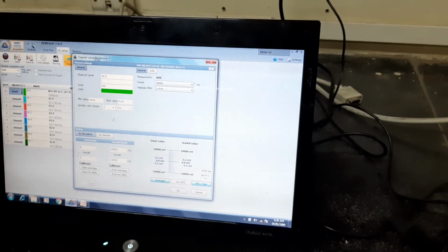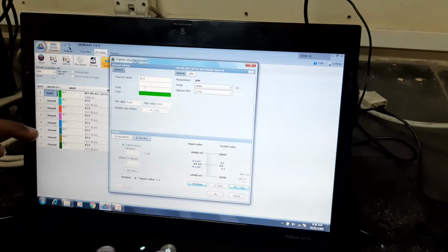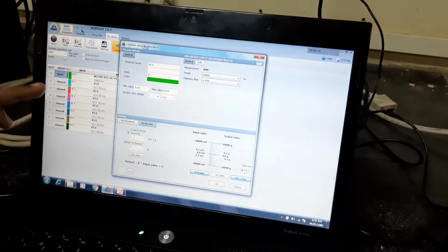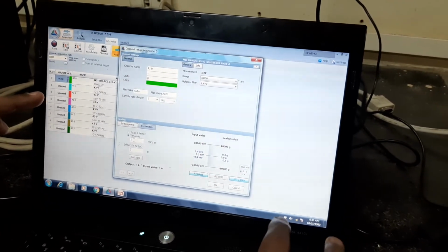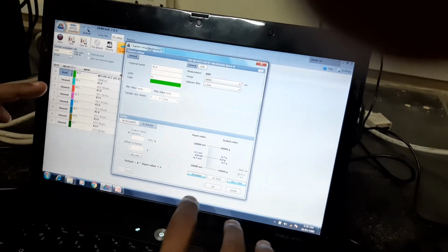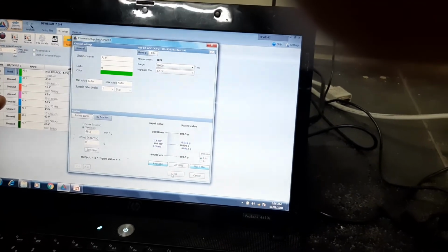Then you have to go to set the channel. This is an important thing. First, for the unit, you have to take it as g. Then you have to go for the sensitivity. You have to set the sensitivity, 0.0985, which is taken as 98.5 directly. It is already there, 98.5. Then you say OK.